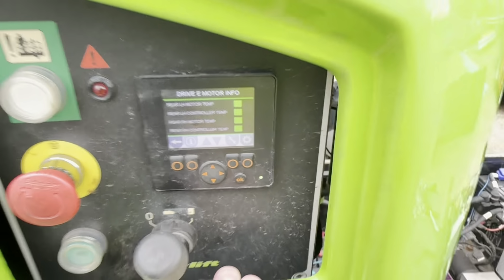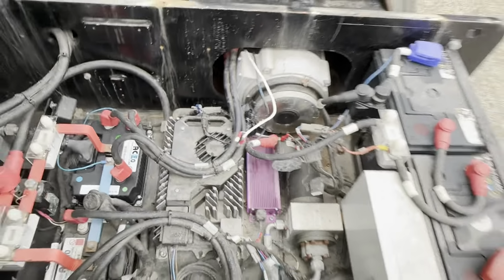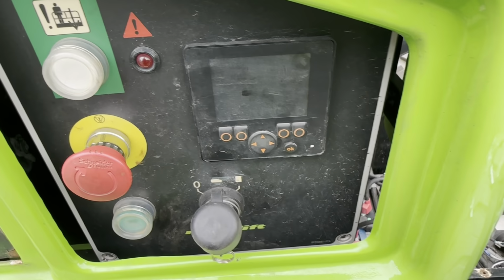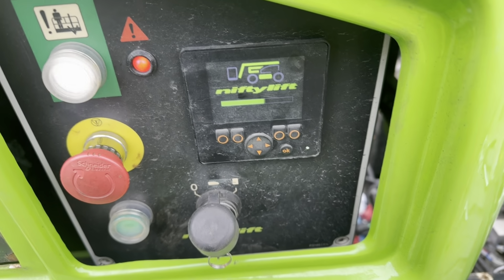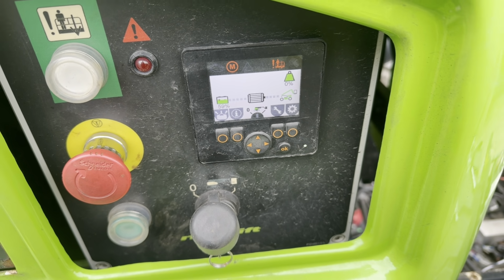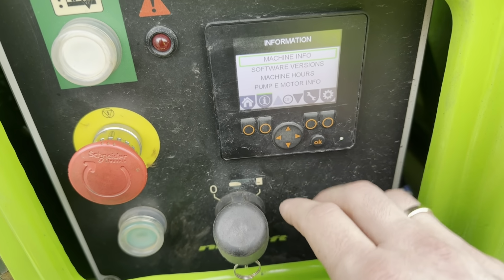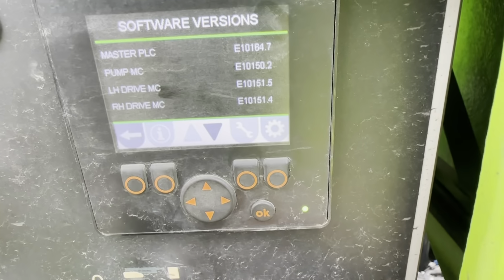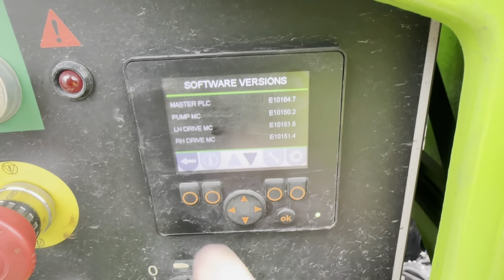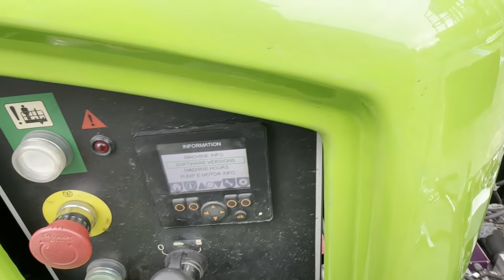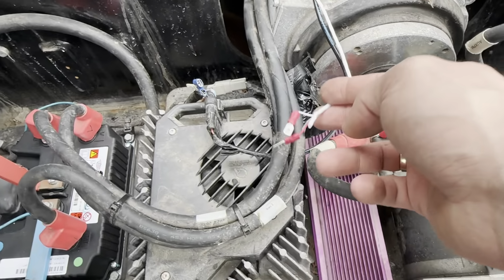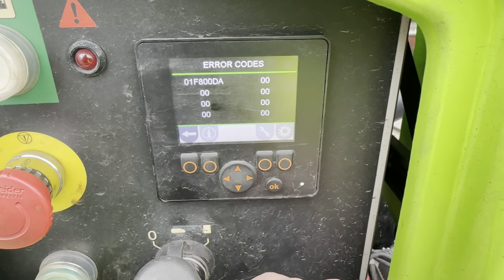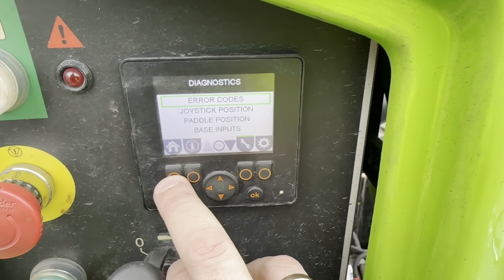These two controllers are on, so obviously everyone is curious now to see what's gonna happen if I disconnect these wires. I wonder if the controller is still not gonna start. So let's do it. So we know for next time, yeah? Controller started, but now it's showing overheat. But if you look into software versions, you see that both controllers are transmitting the software, so the controllers are on regardless of the temperature sensor still being disconnected. Remember, before we disconnected that, the controllers didn't start, and now it's all good.